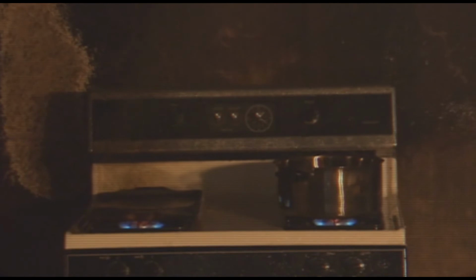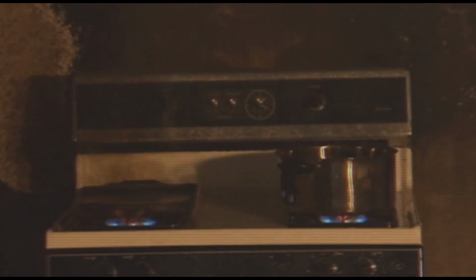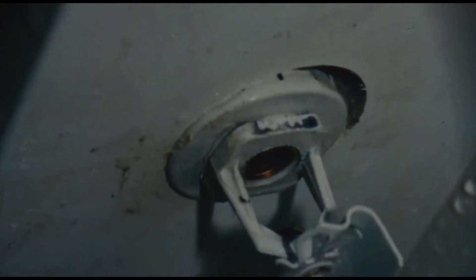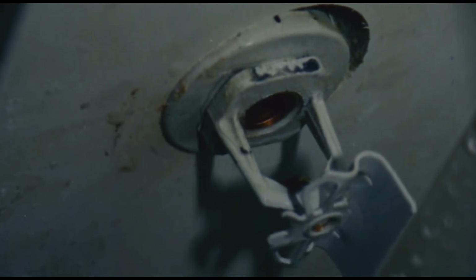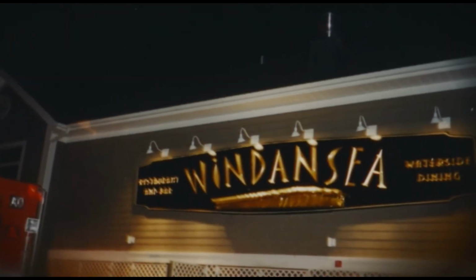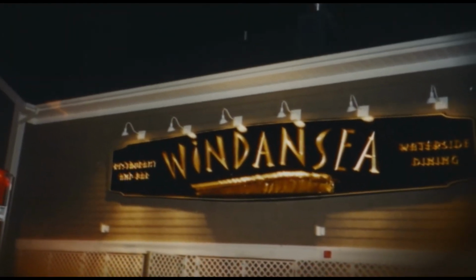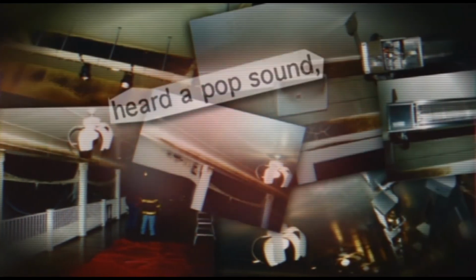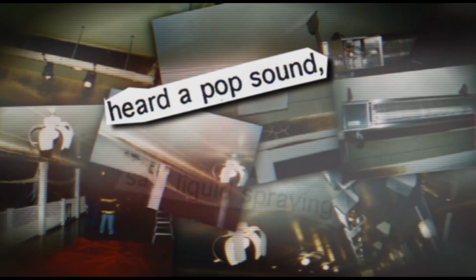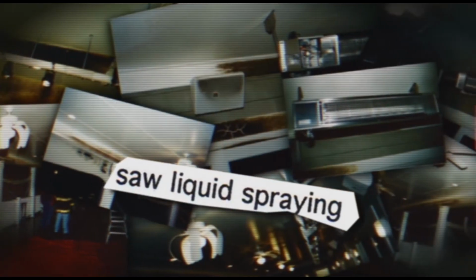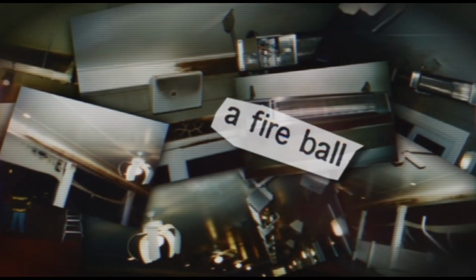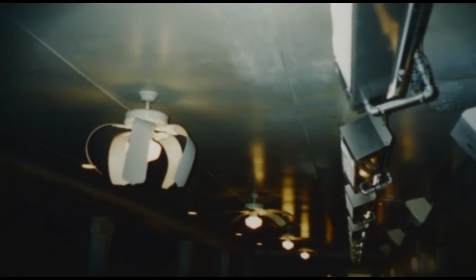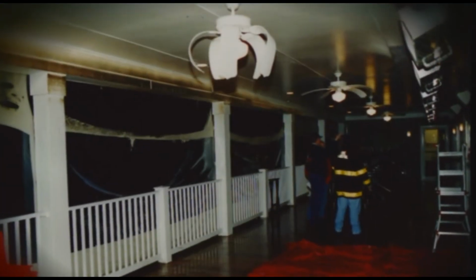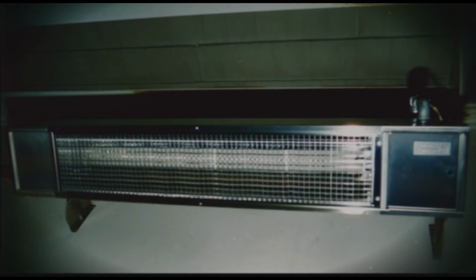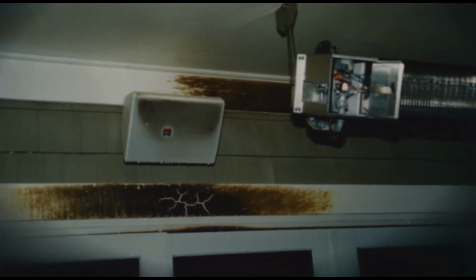That is important because our research found another fire involving a sprinkler system, this one charged with propylene glycol antifreeze, on October 28, 2001 at a restaurant in Highlands, New Jersey. 19 people were hurt as witnesses reported hearing a pop sound, then saw liquid spraying down from above. This was followed by a fireball developing at the ceiling. That blast melted the ceiling fans and blew out windows. Key to the ignition were the overhead heaters that were sprayed by the solution.